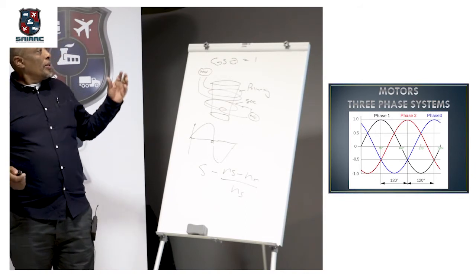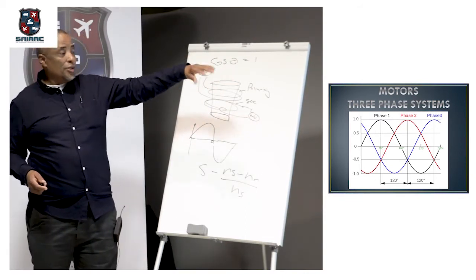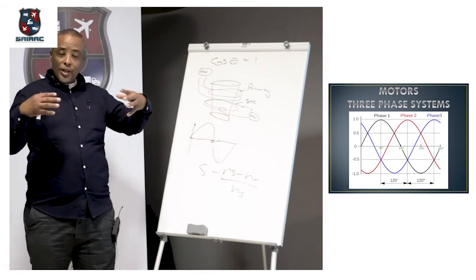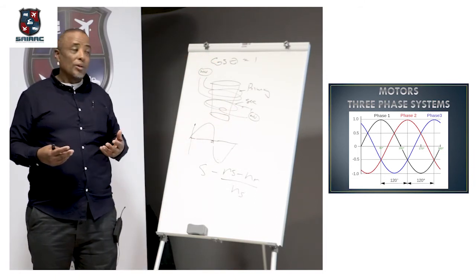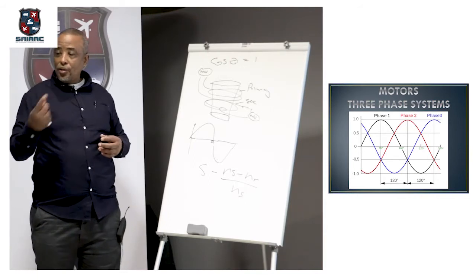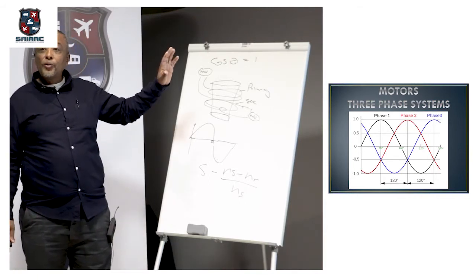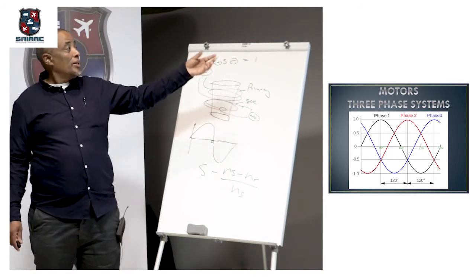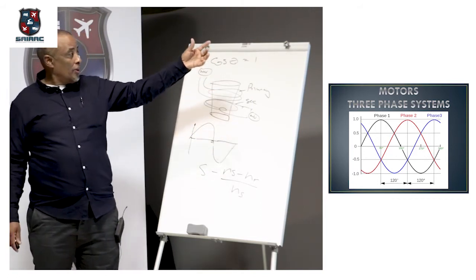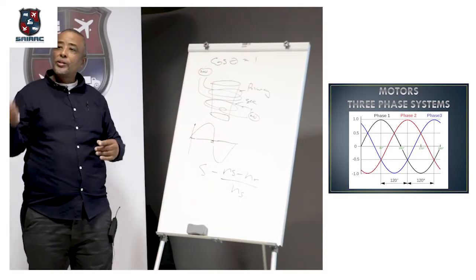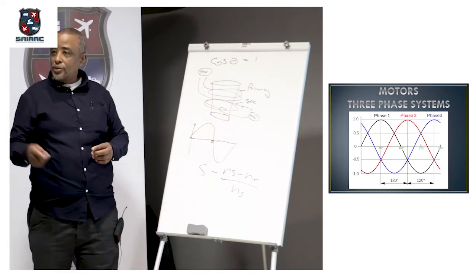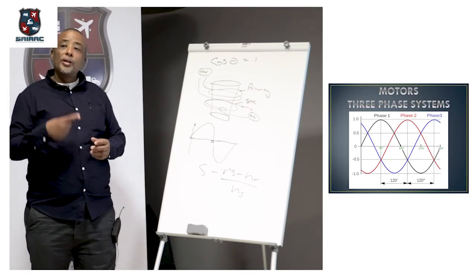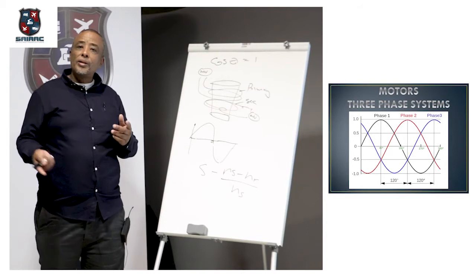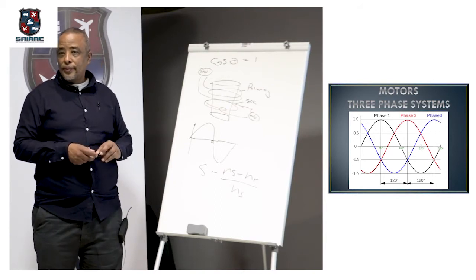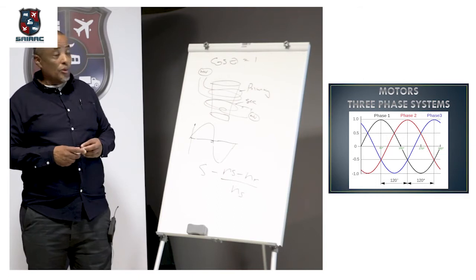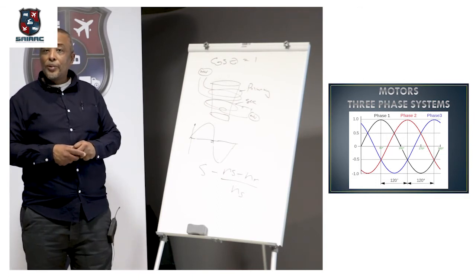Okay, so here we have these 3 windings, each carrying currents. These currents create a magnetic field which rotates around the stator frame at a constant speed. The speed at which it is turning is referred to as synchronous speed. This rotating magnetic field will link with the rotor, which is secondary, and a force will be exerted onto the rotor, which will turn in the direction of the rotating magnetic field, and that's how the motor will turn. If the magnetic field is the other way, it will turn the other way. Okay. All right, that's basically how a motor works, by a rotating magnetic field.